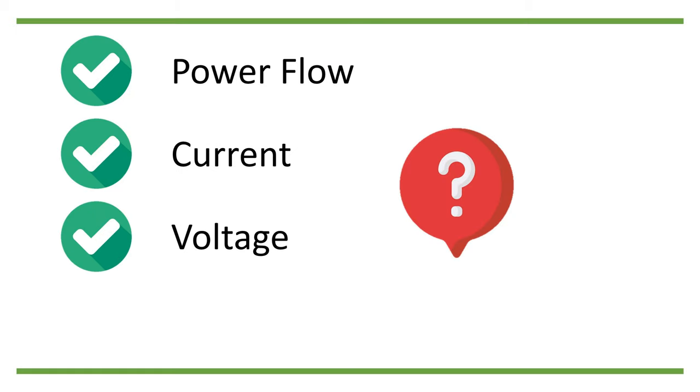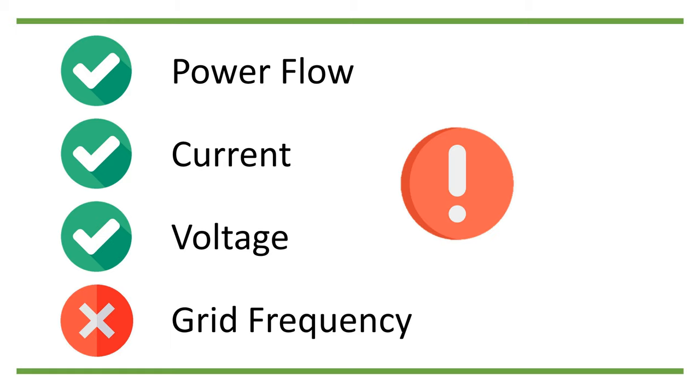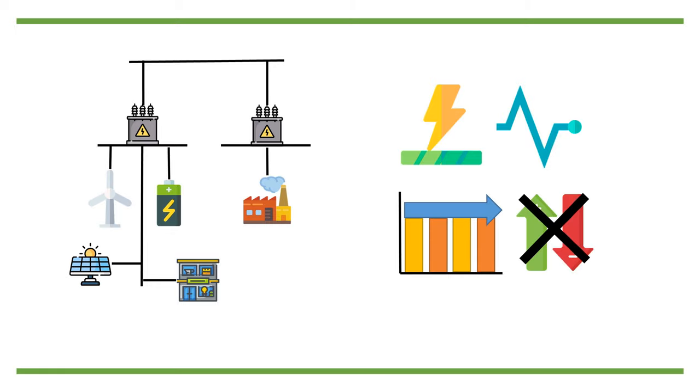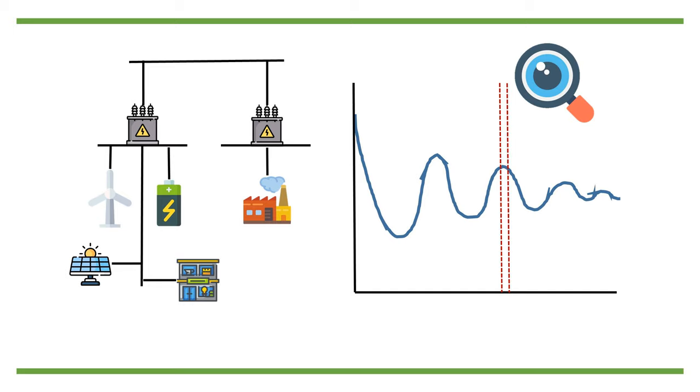However, you probably noticed that something is missing. Grid frequency was not mentioned here. This is because we usually assume the power system is at a fixed stationary point when conducting power flow analysis. So grid frequency does not change at all under this assumption, and it is thus a static analysis of a time slot of the power system.